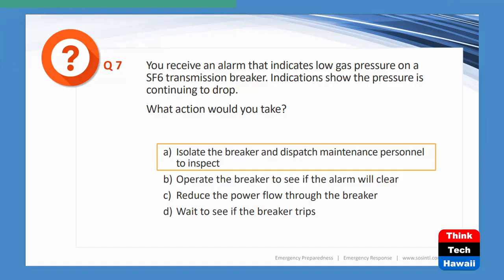So if you lose pressure and you lose gas, then it reduces the ability to not only clear an arc, but then also clear a fault, which is even more severe, right? So usually there are compressors that keep the pressure high, and there's a reservoir tank that keeps supplying it. So if you begin to lose pressure in that particular breaker, you're going to have an issue. So what action would you take?